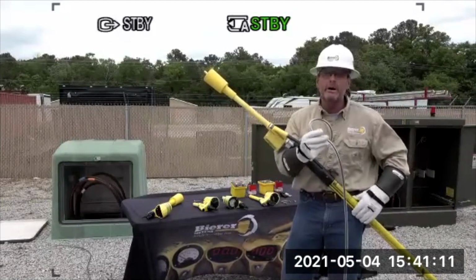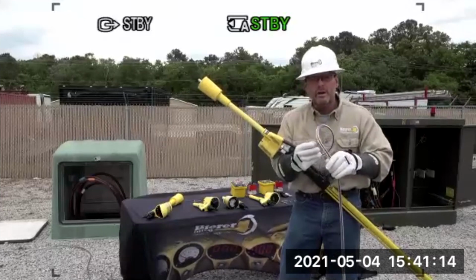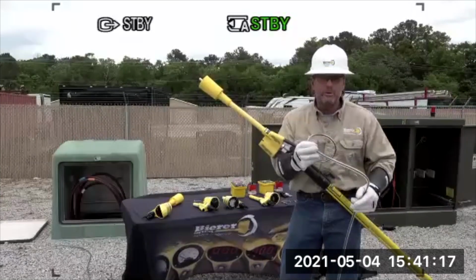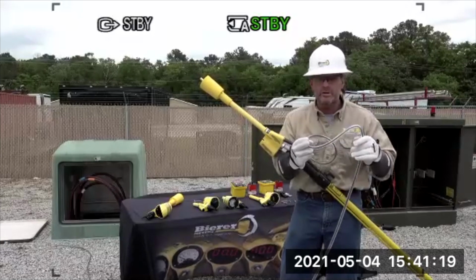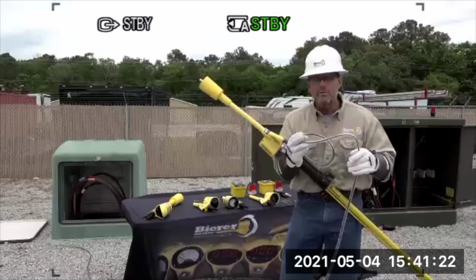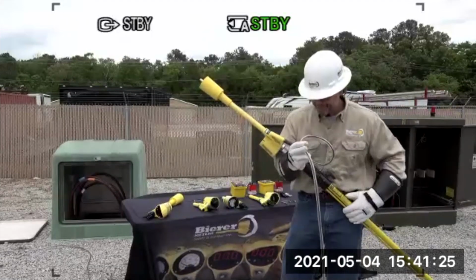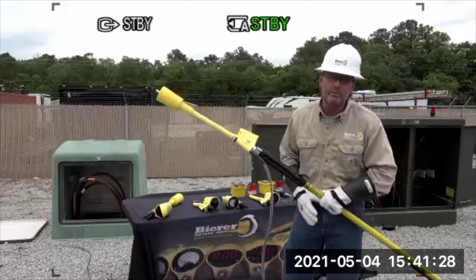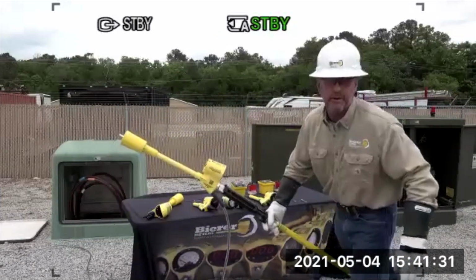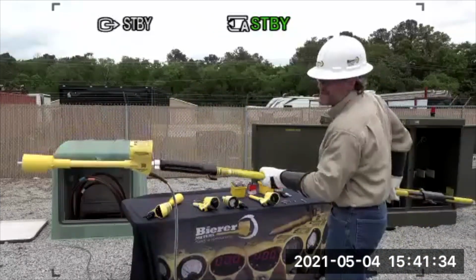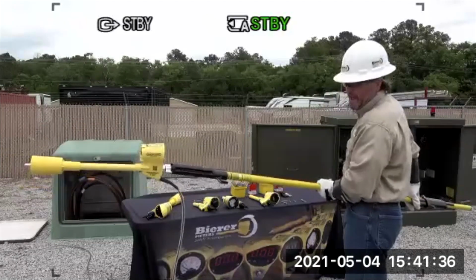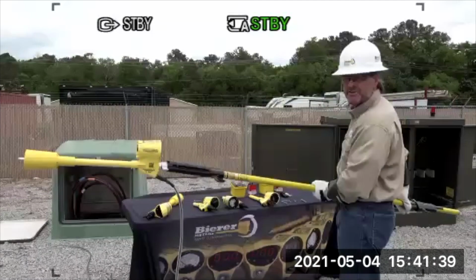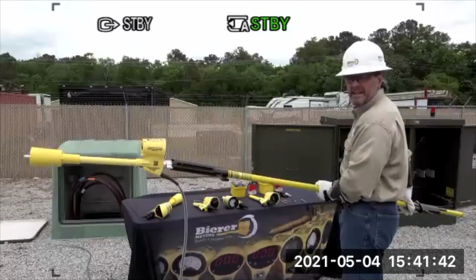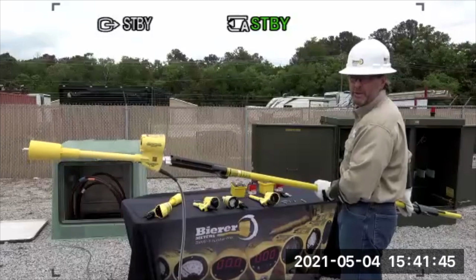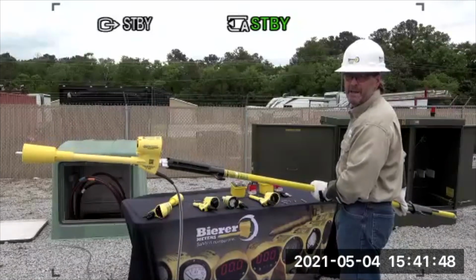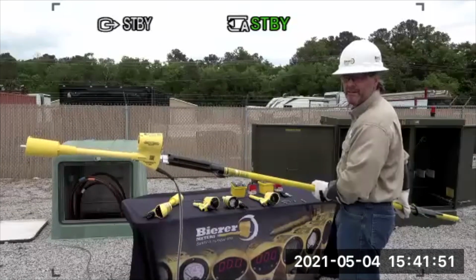So our tools are very safe, but you always want to treat the cord as if it's energized. All the line workers always need to remember that. Even though this cord is shielded at 35 kV, always treat the cord as if it's energized. Whatever distance is written in your work methods for working from the tool, say 36 inches back from the meter head, it's super important that the work methods also state the line worker stays away from the cord 36 inches at the minimum as well. And it needs to be written and understood.